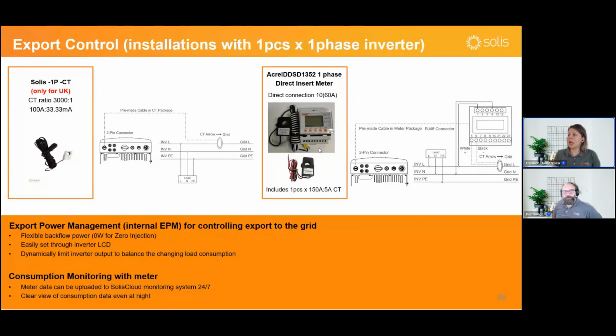Some of them have direct connections. Some of them come with CT clamps to measure the current, and you have all the CT ratio settings, for example, already preset there. You have all the communication addresses and also the settings for the Modbus communication to properly communicate with the inverter. So everything is set up with the meter that we deliver. If you purchase them from somewhere else, that probably is not the case, and you're going to have communication issues between the inverter and the meter.